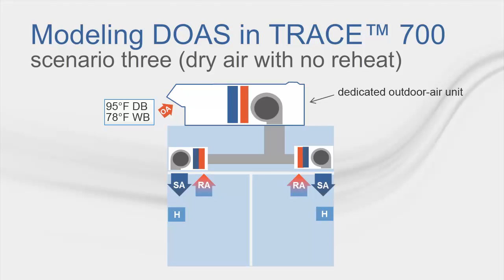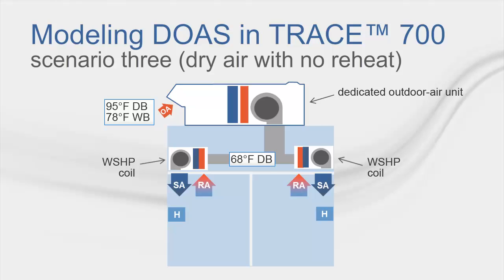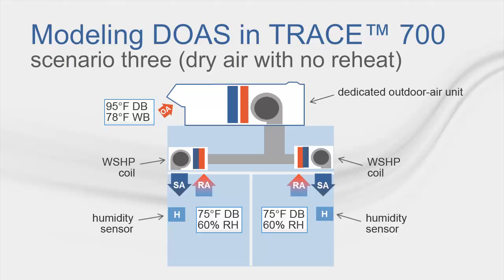For our final scenario, let's consider the same building with water source heat pumps. During the cooling season, the DOA dehumidifies the outdoor air to a 52-degree dew point; however, in this scenario we are not reheating that air to room neutral temperature. During the heating season, the DOA heats the outdoor air to 68 degrees Fahrenheit. Additionally, this building has a system-level controller that uses humidity sensors in the rooms and resets the dew point leaving the DOA up to 60 degrees dew point, preventing relative humidity in the worst-case room from rising above 60% while minimizing energy usage — optimizing the supply dew point to meet dehumidification requirements.